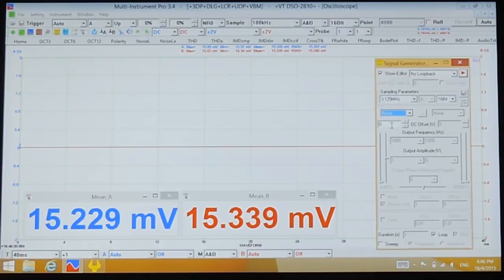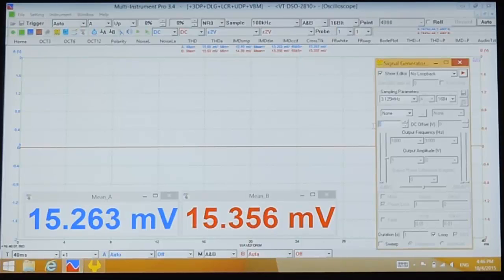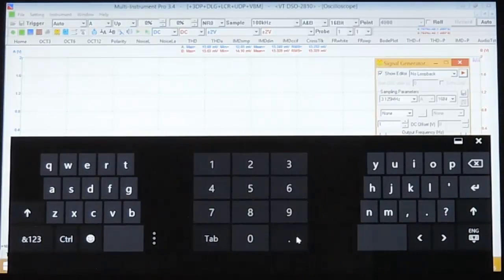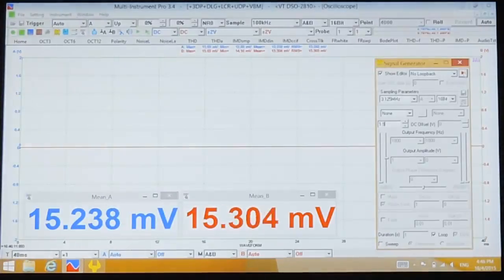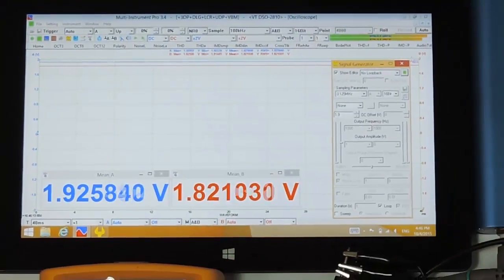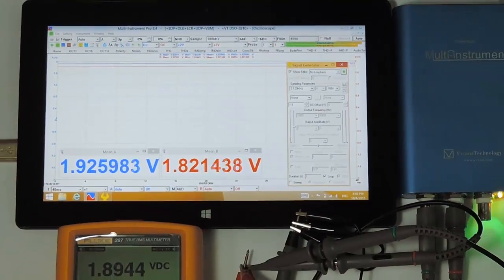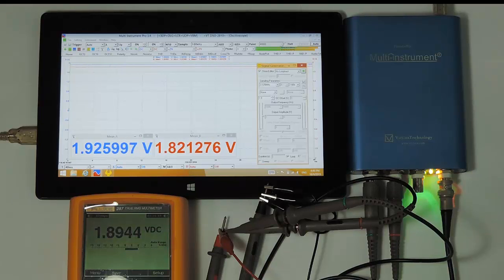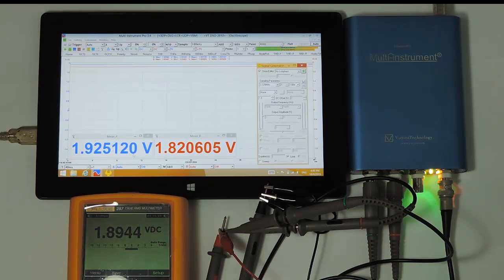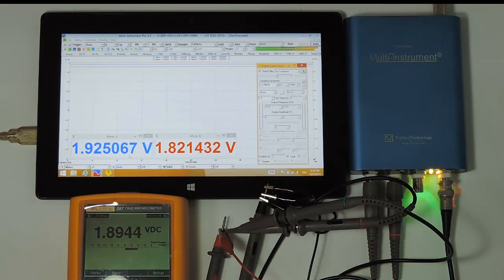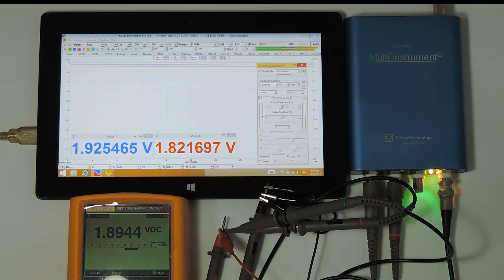We choose 1.9 volts because it's close to the full scale range to be calibrated. Using a too small voltage will affect the calibration accuracy, while using a voltage too close to the full scale voltage may suffer from clipping error. The multimeter shows 1.8944 volts. So we need to adjust the gain for both channels such that the measured voltage is to be the closest to the multimeter display.